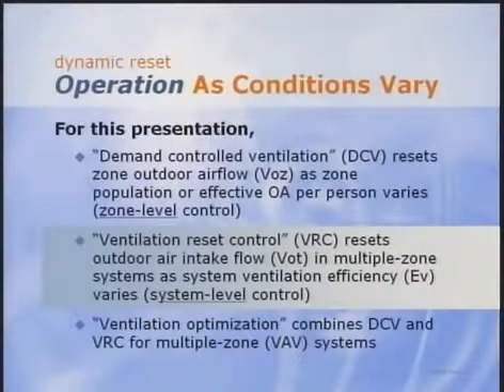As zone airflow changes in response to changing thermal loads, the system ventilation efficiency also changes. So the actual outdoor air needed at the intake is different at part load than at full load. Standard 62 recognizes this and allows optional controls that adjust outdoor air intake flow in response to variations in system ventilation efficiency. We refer to this approach as ventilation reset control. Before I explain this in more detail, let's talk about efficiency.